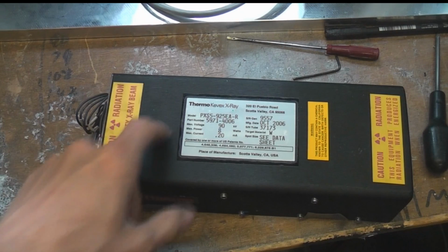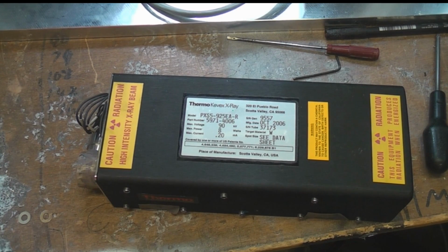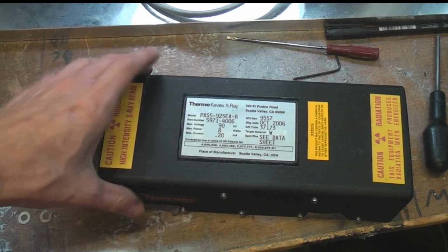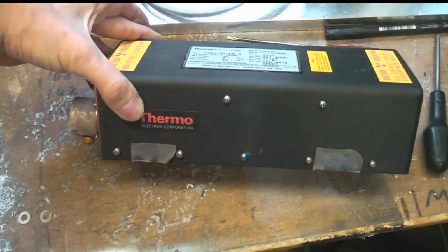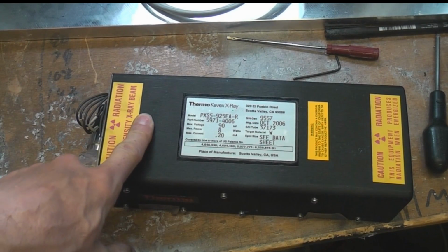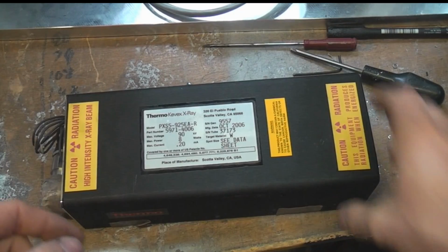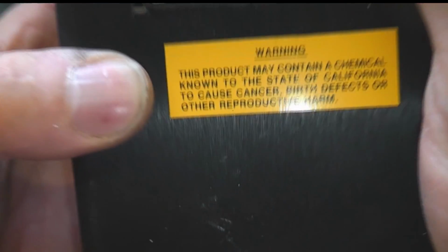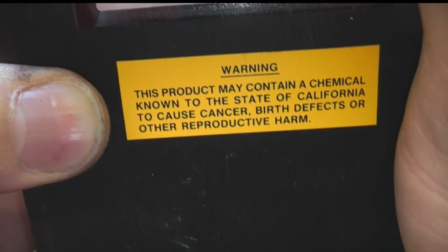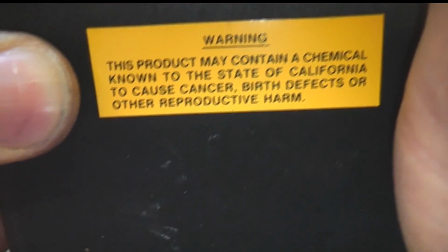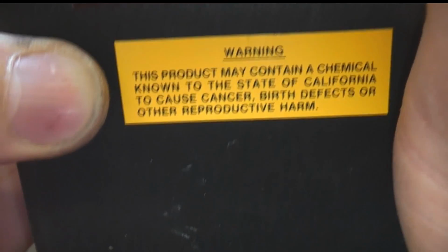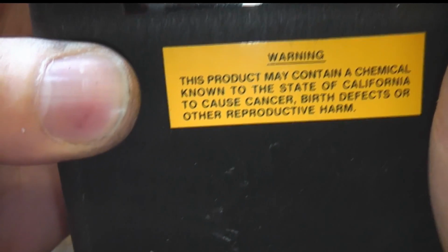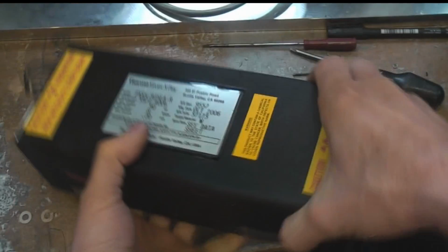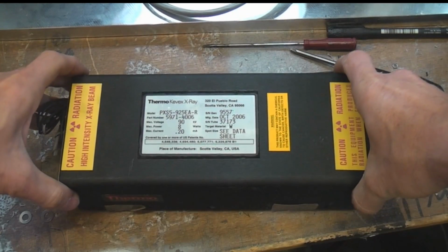Seems a bit of a bodge, but the reason this thing was scrapped was that it's not putting out enough energy, and they say it would cost about 20 grand to replace. I suspect a lot of this might be potted or encapsulated because of the high voltage. It's rated up to 90 kV, so there's clearly going to be some fairly solid insulation in there. And there's a sign saying it may contain a chemical known to cause cancer, birth defects or other reproductive harm. I'm guessing that's referring to the beryllium, but when I was in San Francisco, pretty much every building I went into had a sign saying that outside, so not sure how useful that warning is.